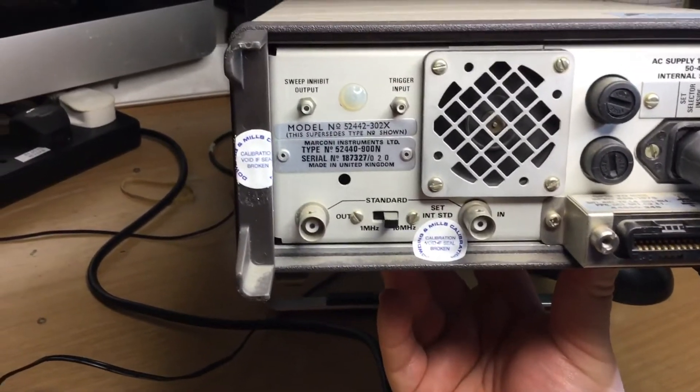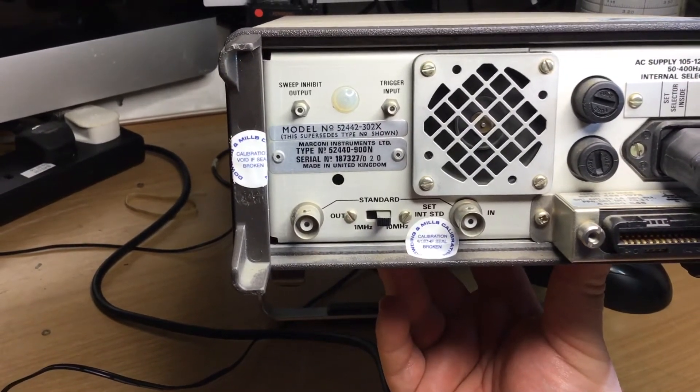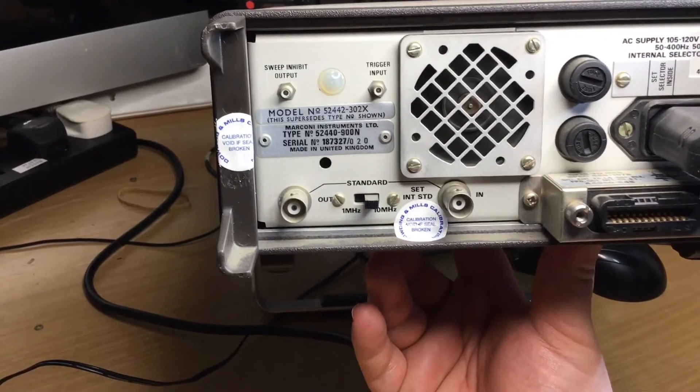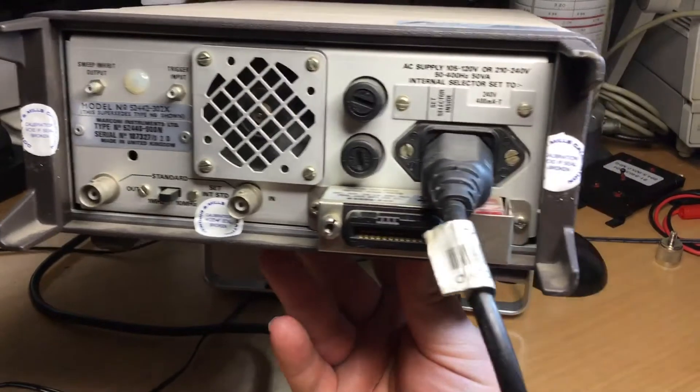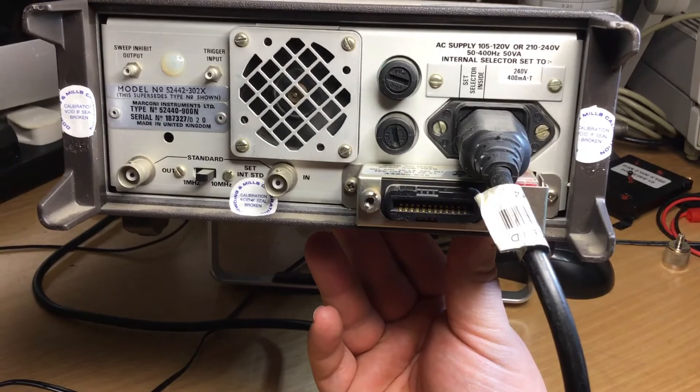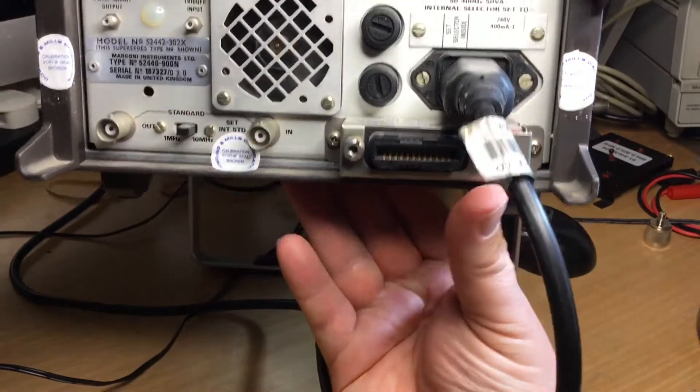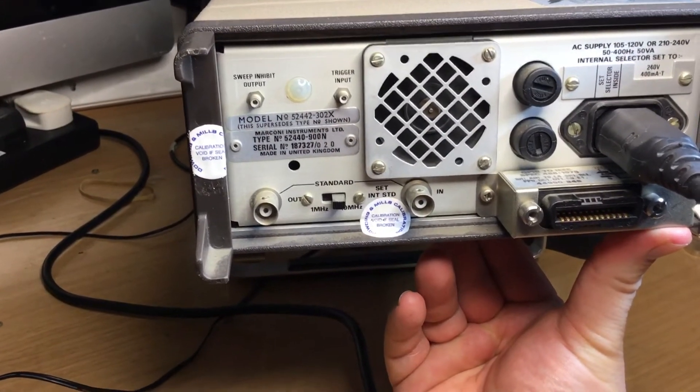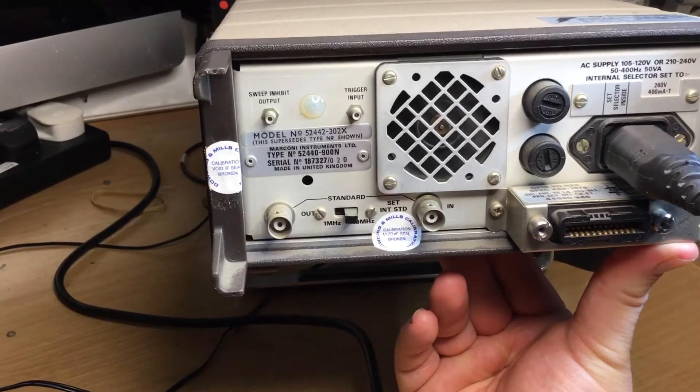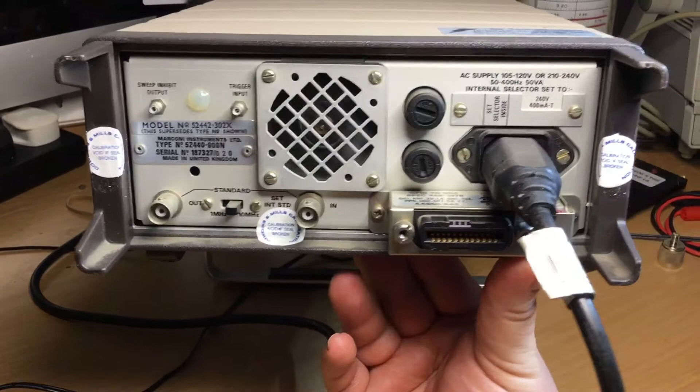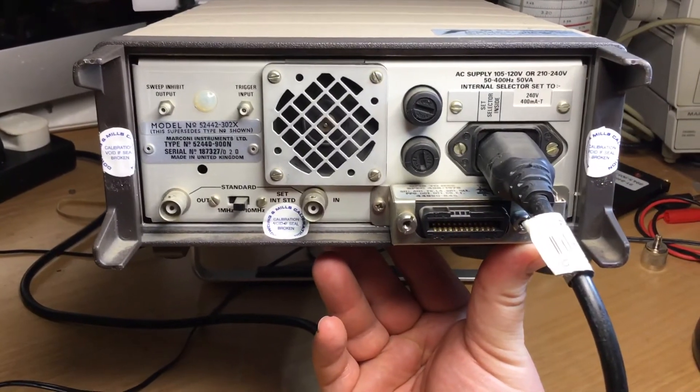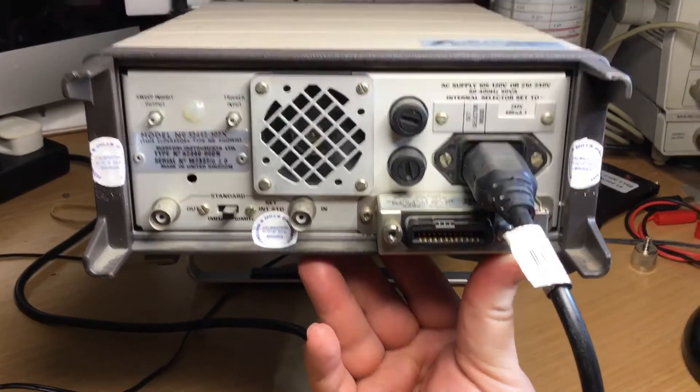So on the rear of the unit, we have a few little things. We've got the frequency standard where we can set it between 10 megahertz or one megahertz. We've also got an in and output port there, so you can run other test instruments from this. We've got the fuses to protect it, and then we've got the GPIB connector. You'll also notice that there's a trigger input and a sweep inhibit output. So these outputs can be used for when we're making measurements with sweep generators and oscillators and we're measuring performances of RF systems. That's a rundown of the back. Obviously we've got a fan. It's quite a quiet instrument to run. Some instruments are very noisy when they're running. This is quite a nice little instrument.